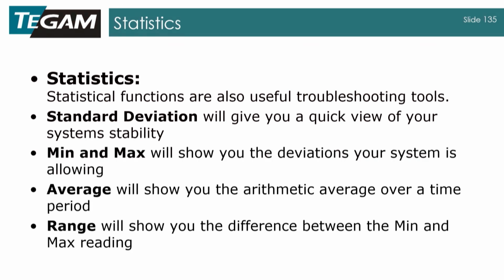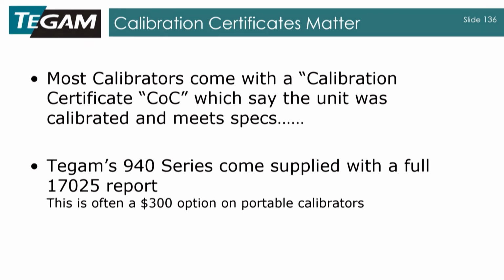Something else we throw into these calibrators that's kind of useful: if you want to do a quick statistical analysis, you can set the calibrator or our thermometers up to collect data, and they'll compute all these statistics. You can monitor a process over a long period of time, and it'll tell you the standard deviation, min and max, and show you all the excursions. For a lot of things, that's all you need, and it doesn't require any special data collection—everything's built right in. It tells you a bit about the capability of your process, and we throw a 17025 cal report in with our new calibrators too.